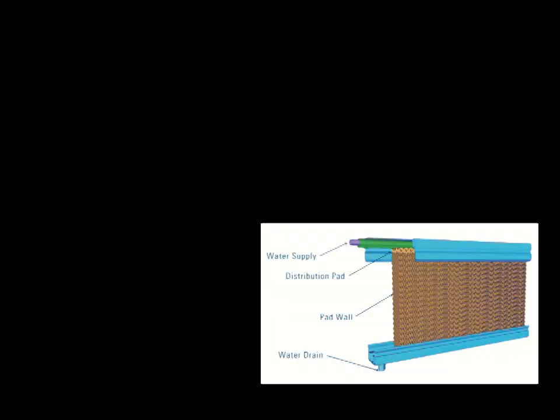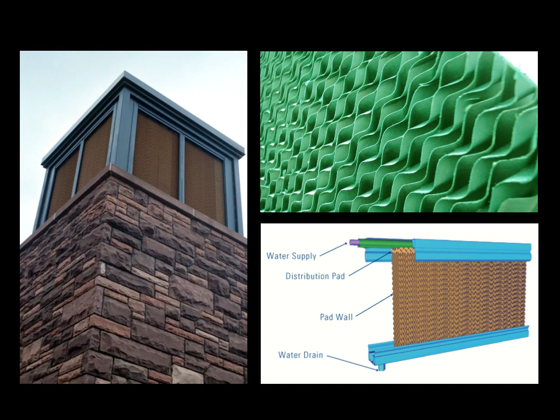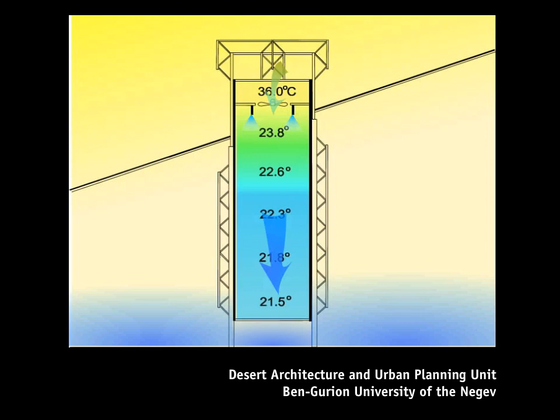You can see there's this kind of top or head on the evaporative cooling tower. That's the downdraft part. So this would have a kind of sponge-like medium. Could be rock wool or a kind of vegetable fiber or some kind of a synthetic fiber. Anyhow, it's a mat that's full of moisture. There's a little pump that trickles the moisture down through this sponge-like material. It's also permeable to air, so the air can move through it. As the air moves through it, it picks up moisture. As it picks up that moisture, it becomes more humid, so the moisture is added to the air. And at the same time, the dry bulb temperature is dropping. So the humidity goes up, the absolute humidity goes up, and the dry bulb temperature goes down.